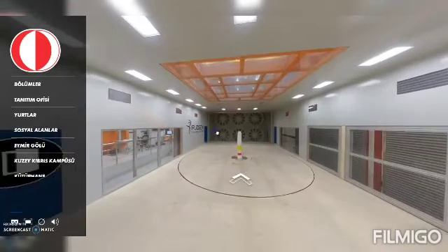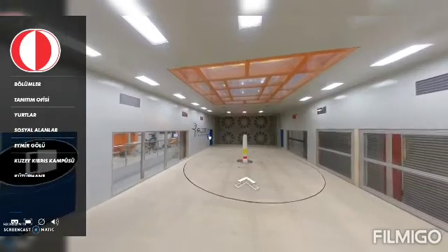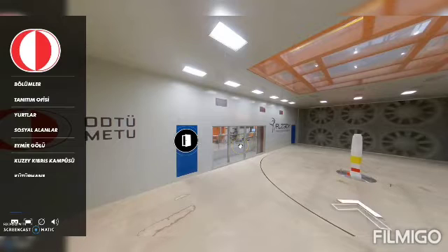In the test section over here, in this black part, we have a honeycomb. Turning around now, we have the full view of the atmospheric boundary layer test section with the turntable model placed and the fans all the way back. In this test section we can go up to 30 meters per second wind speed at maximum fan power of 2.4 megawatts. That 2.4 megawatts is about one third of the total power required by the METU campus.